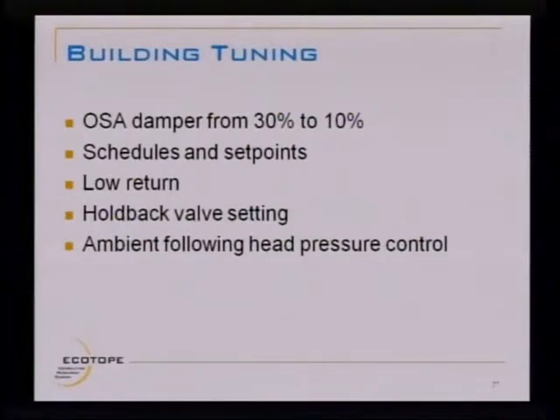In fact, set it as high as you want. Set it to 72 degrees. Try to get the store up to that. Most of the time you can't get that much heat out of the refrigeration system to get the store that hot. And then you can manipulate the set point on the gas at night. We added a low return, which made a huge difference that I'll show you in a minute.